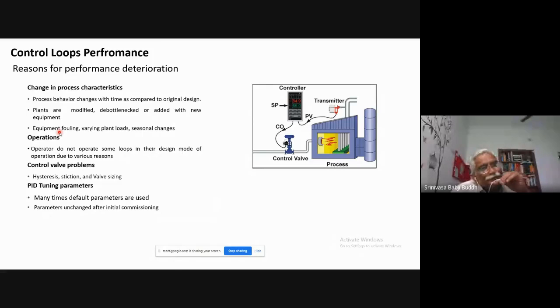Then seasonal changes, summer and winter, particularly in North India, where you have a drastic difference between summer and winter in the environment temperatures. That also will have an impact on the heat exchanger performance. So all these factors result in change in the process behavior, which in turn will affect the performance of the PID controllers. And sometimes operators also keep some of the loops in manual and operate the plant because there are some issues, like maybe some design issue or tuning issue, because of which they are not able to operate these loops in automatic mode.